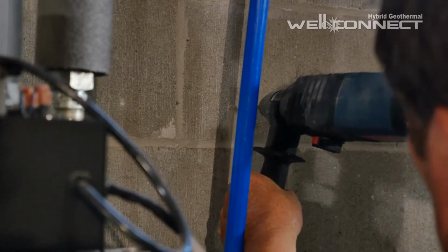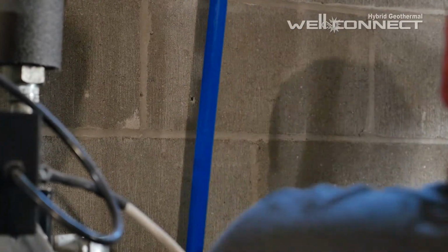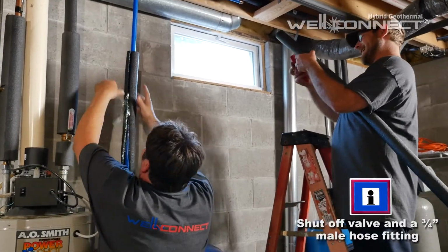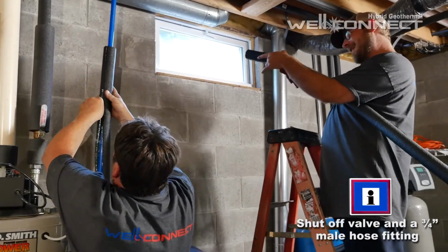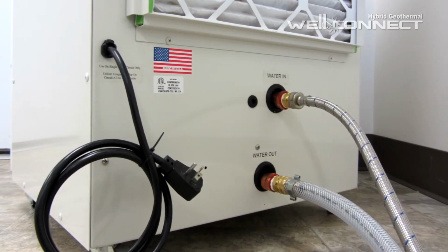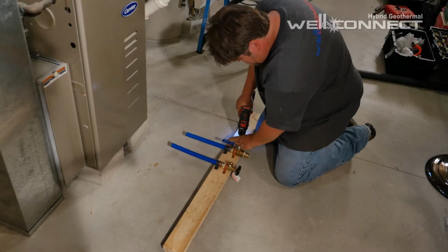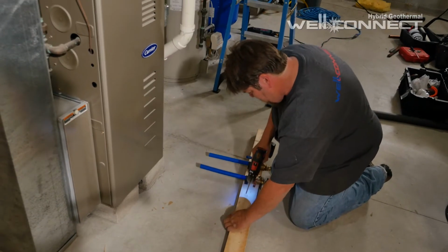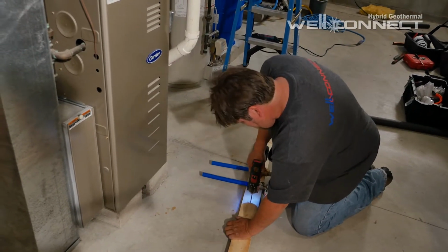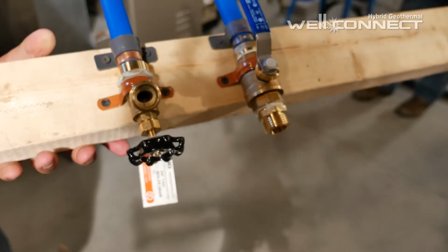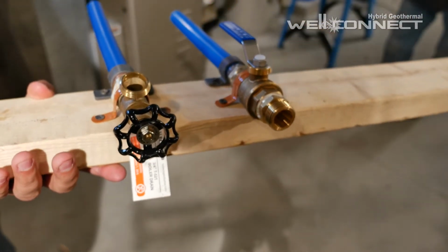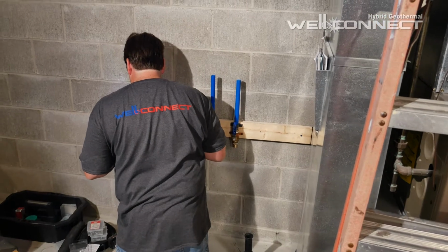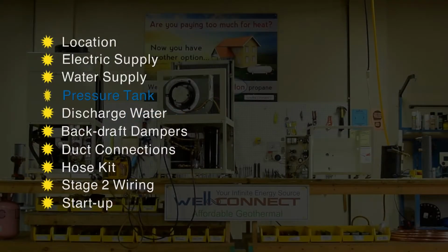The water supply piping should be insulated and properly secured, terminating with a shut-off valve and a 3/4 inch male hose fitting secured within a few feet of the WellConnect hose connections found on the lower rear side of the unit. For poured or concrete block basement walls, it is often a good idea to mount a 12 inch to 18 inch section of 2x4 lumber to the wall using Tapcon fasteners, and then mount the supply and discharge pipe fittings to the 2x4.